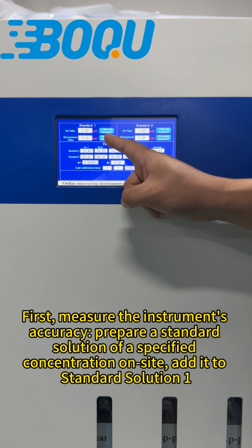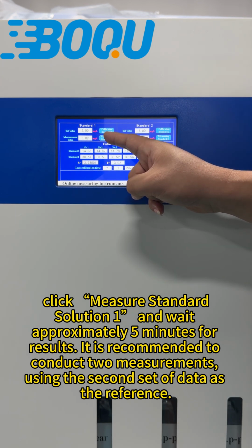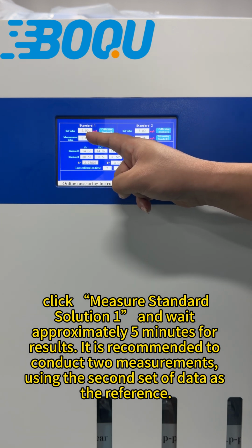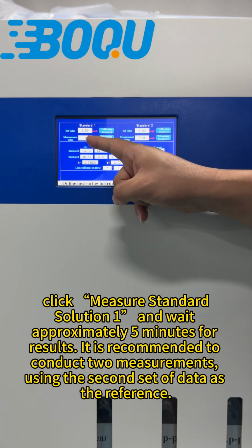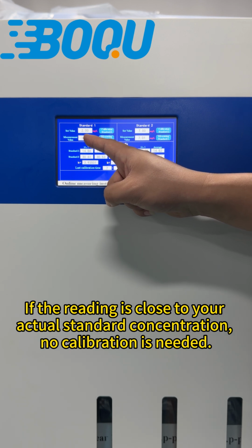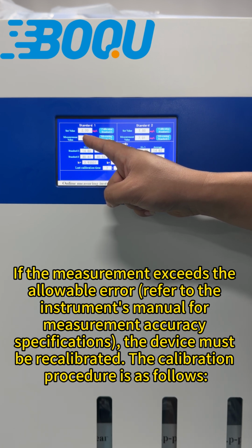Prepare a standard solution of a specified concentration on site. Add it to standard solution 1. Click Measure standard solution 1 and wait approximately 5 minutes for results. It is recommended to conduct 2 measurements using the second set of data as the reference. If the reading is close to your actual standard concentration, no calibration is needed. If the measurement exceeds the allowable error, refer to the instrument's manual for measurement accuracy specifications. The device must be recalibrated.